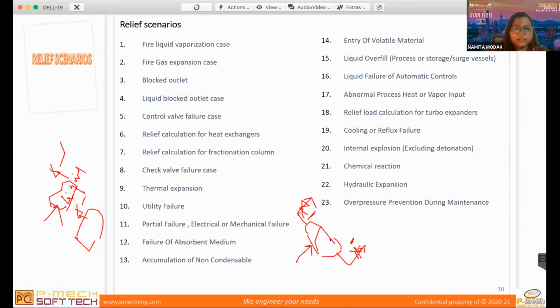Then control valve failure case. If you have a control valve at the inlet, many times we give a bypass for the operation of this control valve. If your control valve fails, fail means full opening of this control valve. Whatever the normal flow rate, let's say it's coming at X, it can be fully open at maybe 2X. So the 2X starts pressurizing your system.